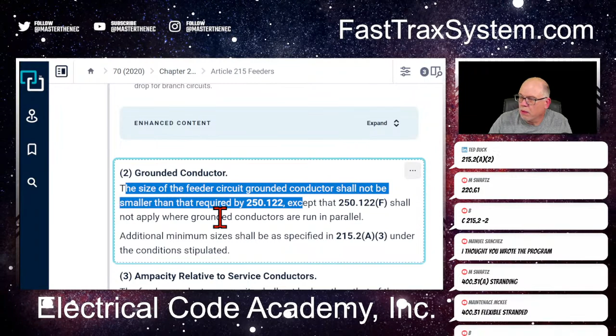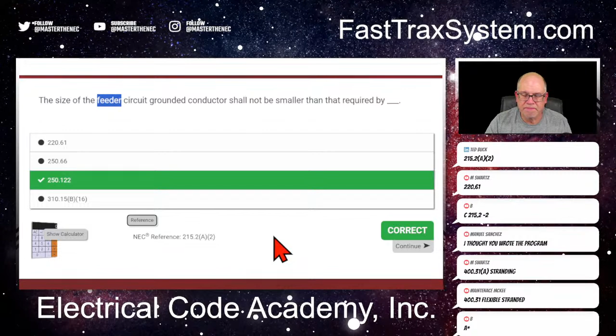So let's go back to the lesson here. So that's just like a minimum size rule for the feeder. Minimum size rule for the grounded conductor. So right there, and there's the reference 215.2(A)(2). Okay. So again, the trigger in that one is feeder. Then you've got to know Article 215. And Article 215 is not big at all. So at that point, you would know to just bold scan, and you'll see the grounded conductor size.